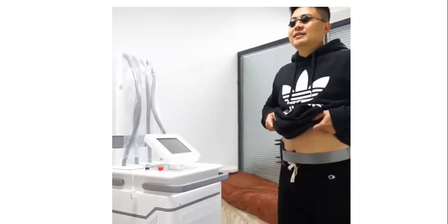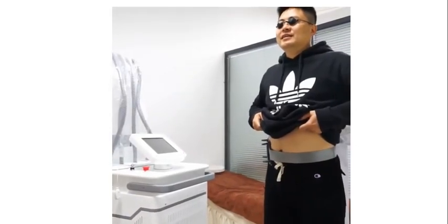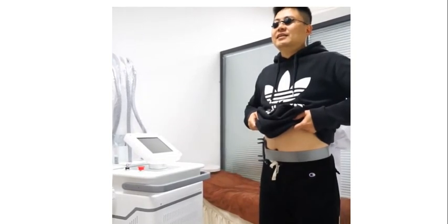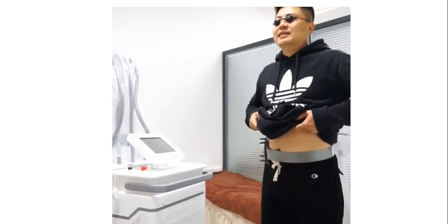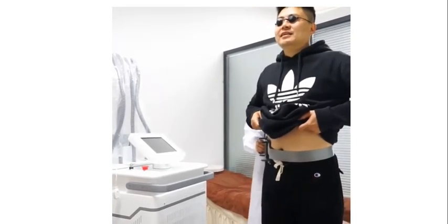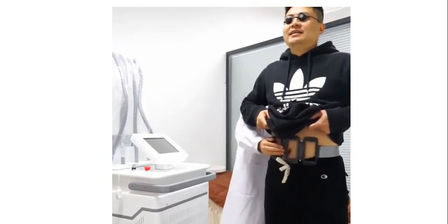Now we show how to operate. Fix the handle connectors with the patient's treatment parts tightly. Please note that we prepare six handle connectors. Four handle connectors are for large treatment areas such as the abdomen.